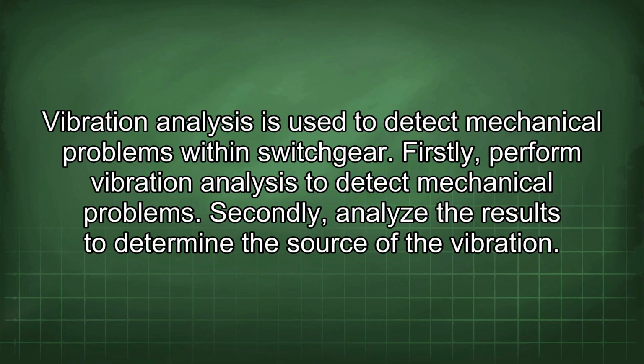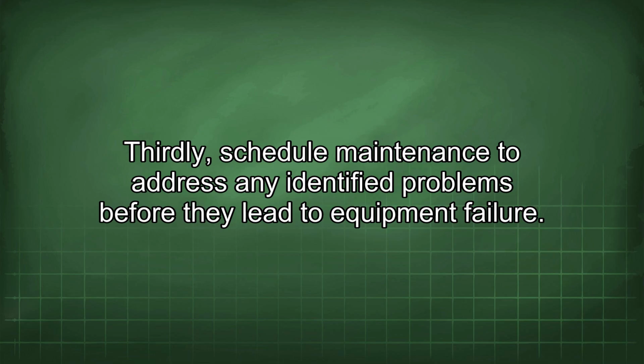Vibration analysis is used to detect mechanical problems within switchgear. Firstly, perform vibration analysis to detect mechanical problems. Secondly, analyze the results to determine the source of the vibration. Thirdly, schedule maintenance to address any identified problems before they lead to equipment failure.